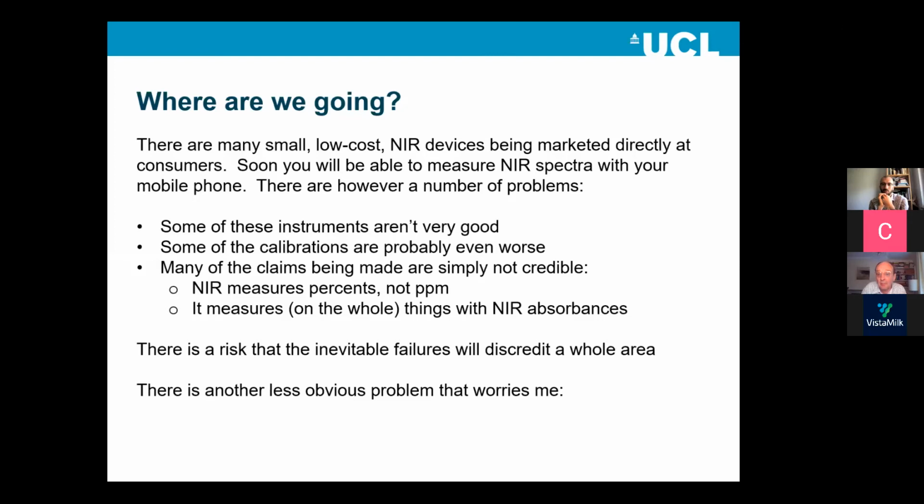There's lots of stuff on the internet if you just search on these things, saying how wonderful they are. You see people standing up or sitting in discussions at conferences saying how wonderful they are, and it's not always true. Some of the instruments aren't very good. Some of them actually don't exist. If you search, you'll find websites for instruments which are really aimed at raising capital in order to produce the instrument. So it takes you a while to realize that this instrument doesn't exist yet. It's a concept. But some of the ones that do exist aren't very good. They're not stable. They're very noisy. And they're marketed with calibrations that don't work. I think the calibrations tend to be even worse.